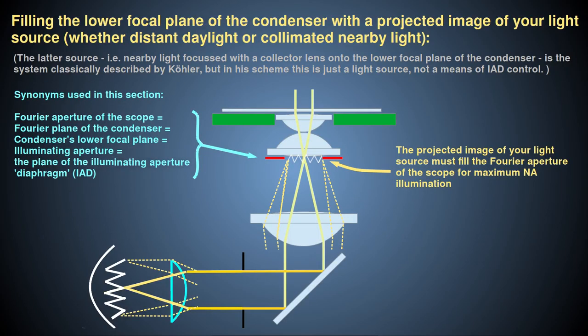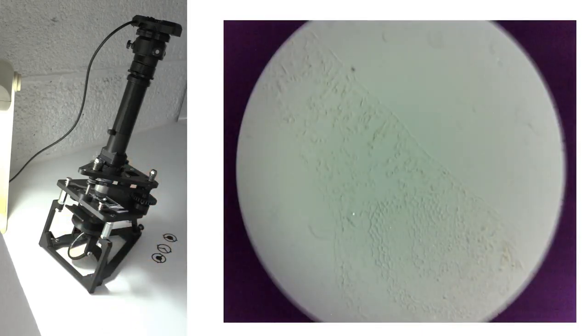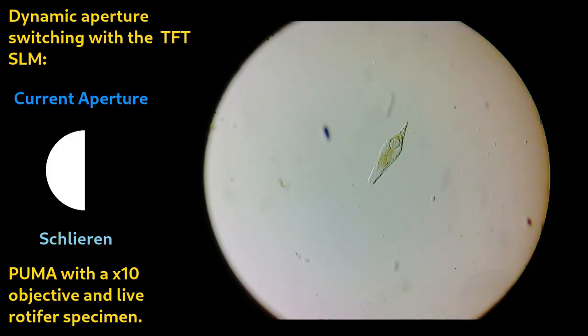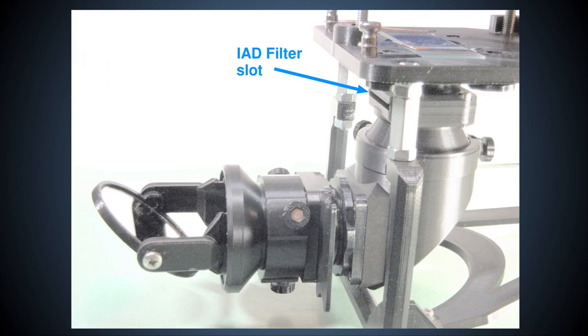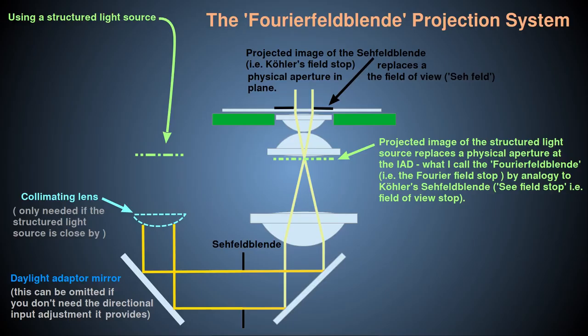The illumination criteria discussed so far are those that are needed for plain full-aperture illumination. However, there may be instances where you do not want the full aperture of the condenser to be illuminated. Some obvious examples are when you want to do Schlieren phase imaging, or dark ground microscopy. This daylight module opens up new opportunities on how to achieve this. The standard way to shape the condenser's lower focal plane is with a solid filter, or the spatial light modulator, or SLM, in the illuminating aperture diaphragm slot, or IAD slot. And you can still do it that way with this daylight module.